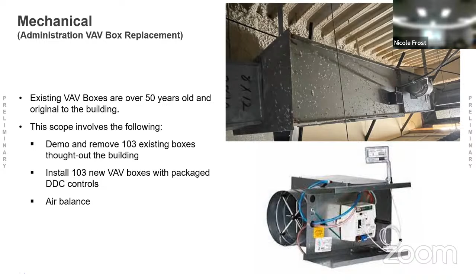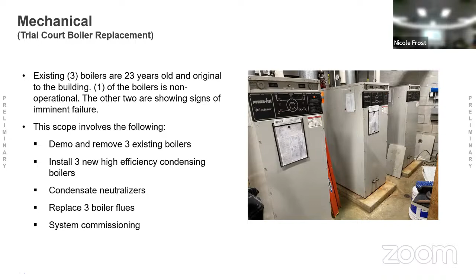Boiler replacement over at the trial court - 3 boilers over there are original to that building, which is about 23 years old. One of which is kind of condemned and was used for parts, so there's really 2 boilers there, both at the end of their life, and could benefit from higher efficiency as well. So the scope involves replacing those 3 boilers with new high efficiency boilers, and all the associated engineering and venting. One thing we're looking at on those is condensate neutralizers, because those are condensing units and condensate can be acidic, so there's a neutralizer on the condensate to make sure we're not rotting out drains and stuff.